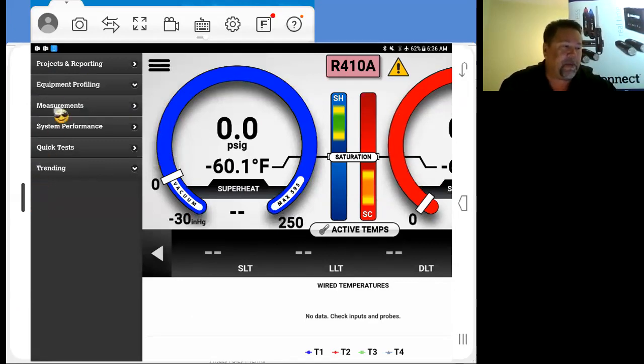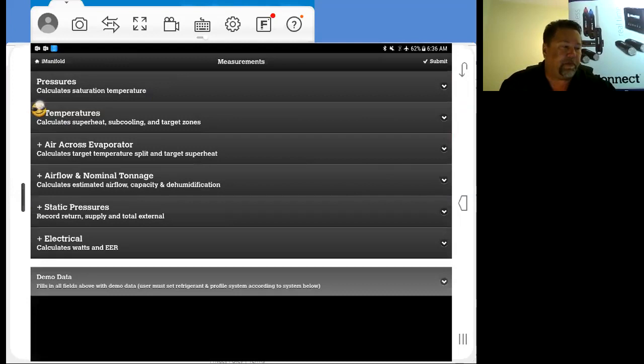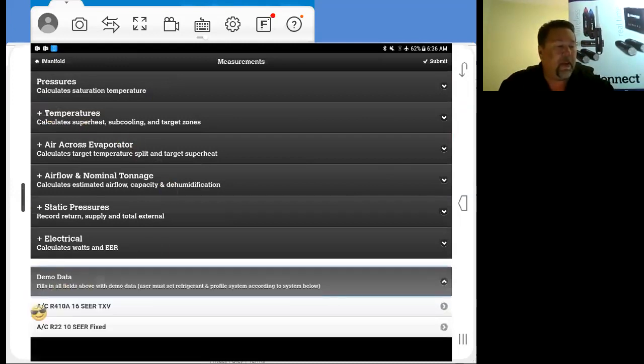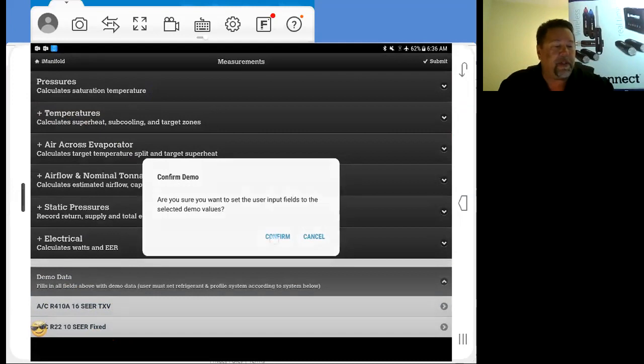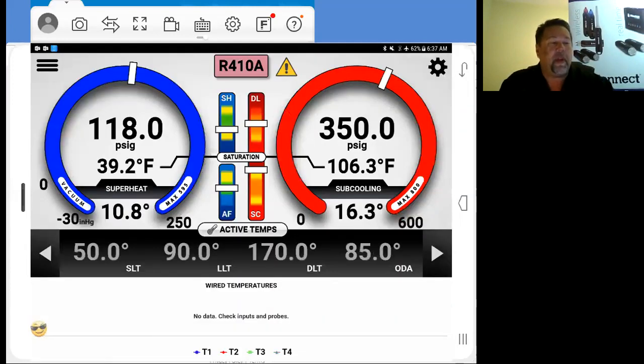So I'm going to go to our measurements tab, open up measurements. All the way down here at the bottom, it says demo data. Open this up. And as you can see, I've got AC 410A, 16 SEER TXV. Now I'm going to go ahead and use that. And we're going to confirm this demo. As you can see, what it did right now was just populate a whole bunch of numbers here. We don't have any targets displayed. Gosh darn it. We don't have any targets displayed.